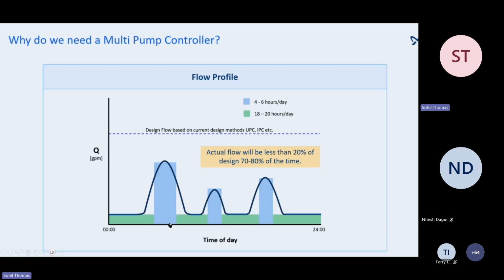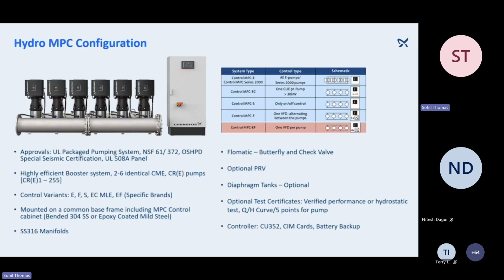If you see on the screen, what you see as green would be where the pump is operating the majority of the time, which is 18 to 20 hours throughout the day, at part load. So the actual flow is less than 20% of the design flow, and that is running 70 to 80% of the time. So that is why we need a multi-pump controller. Why do we have this system in place?